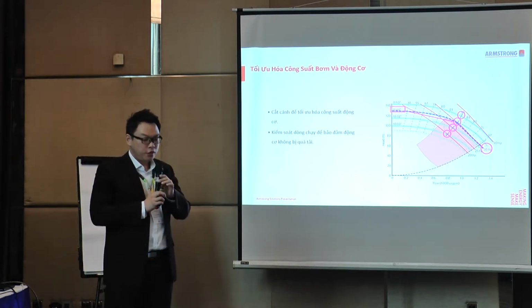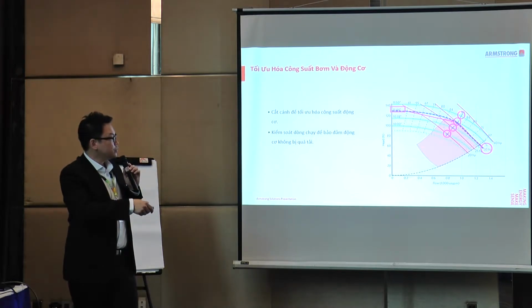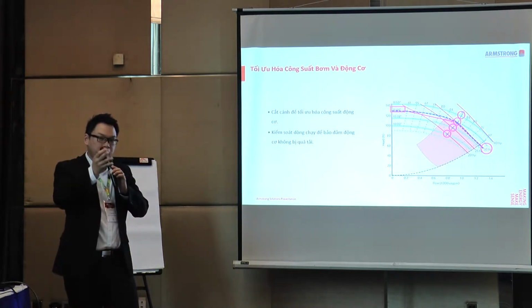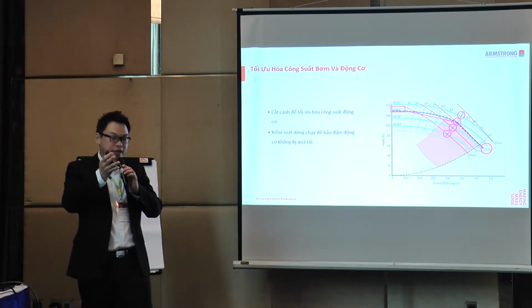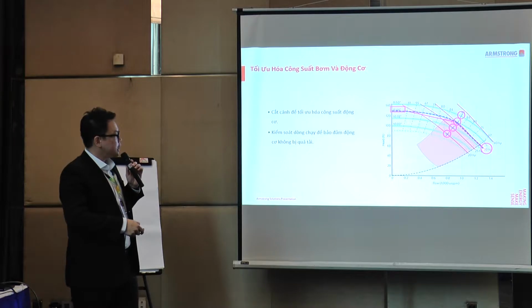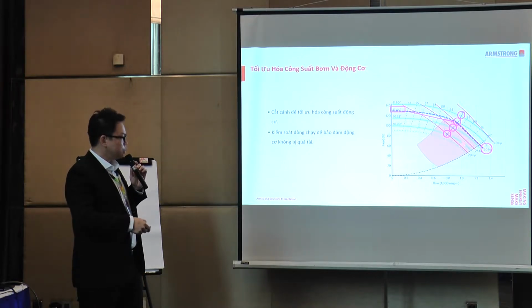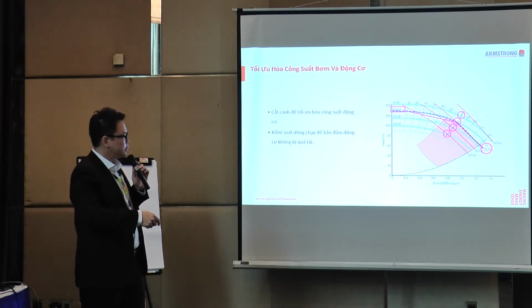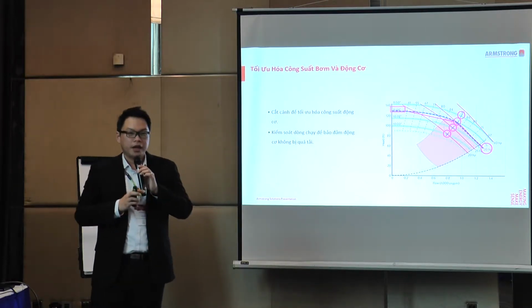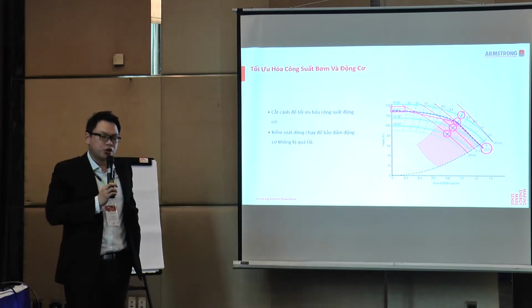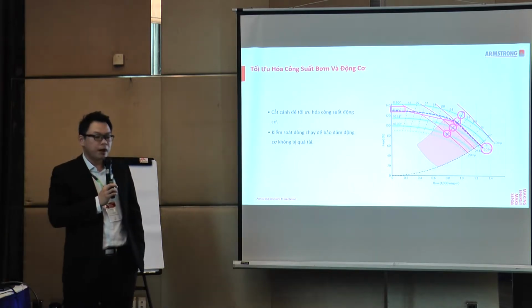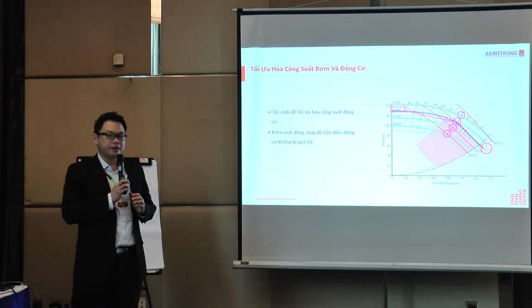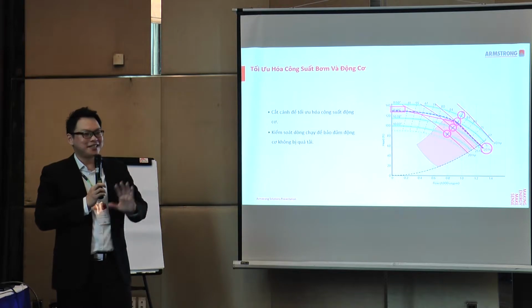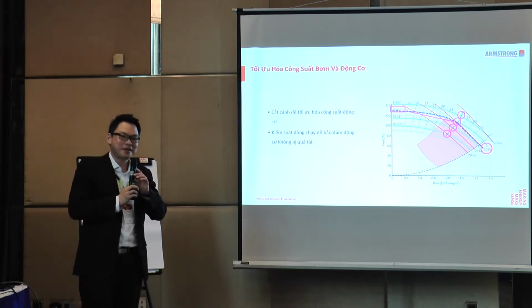So what does this mean? You'll realize that there are these circles here. These circles indicate where the best efficiency points are for each of the impeller sizes. And there is an intersection between the motor curve and the best efficiency point over here. So we'll ride along this curve downwards, and where this intersection is, it will drive all the way down to the end of the curve. This is what we call electronic load limiting, a capability within our pump to ensure that the motor horsepower is not exceeded. It's a lot of words, but I hope you understand my explanation.